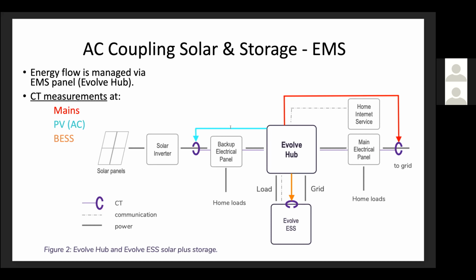The CT measurements are how the hub, or the EMC within the EMS, knows what's happening behind the meter and is able to maintain net zero at the utility meter. So there's a set of mains or load CTs placed at the main service panel, measuring import and export to and from the grid. There's a CT measuring PV. Now, whether it's just PV that's going through the battery system or if it's extra PV, all of the PV needs to be measured in order to get a true net zero, as much as the battery is able to charge to maintain that net zero.